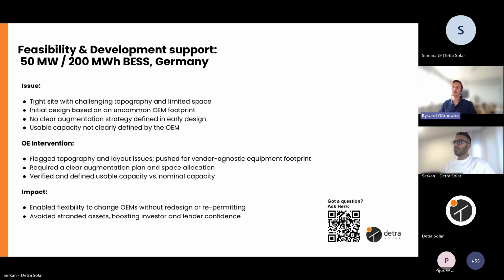Secondly, always define usable capacity in your projects and not just nominal ratings, because those are what drive the revenue. Usable capacity is often significantly lower than the nameplate due to depth of discharge and state of charge limits. And lastly, I'd recommend defining the augmentation strategy or capacity retention from day one.